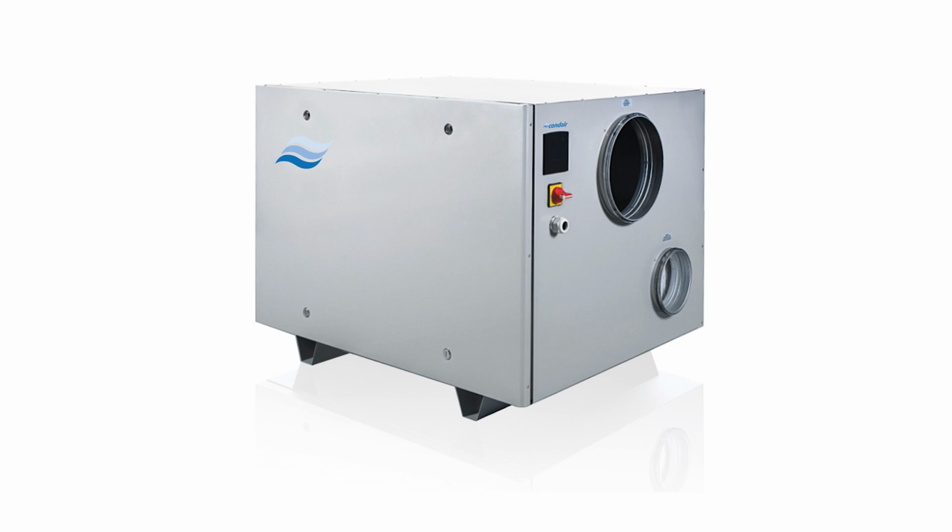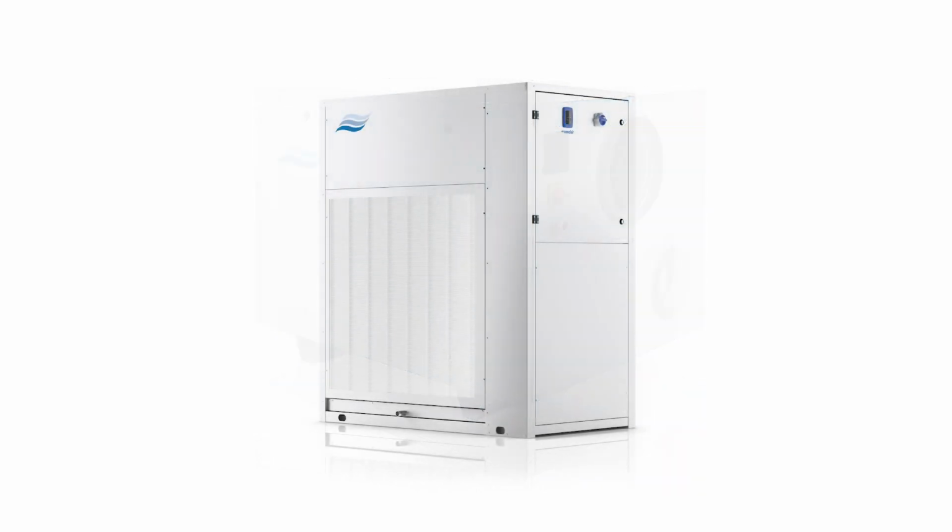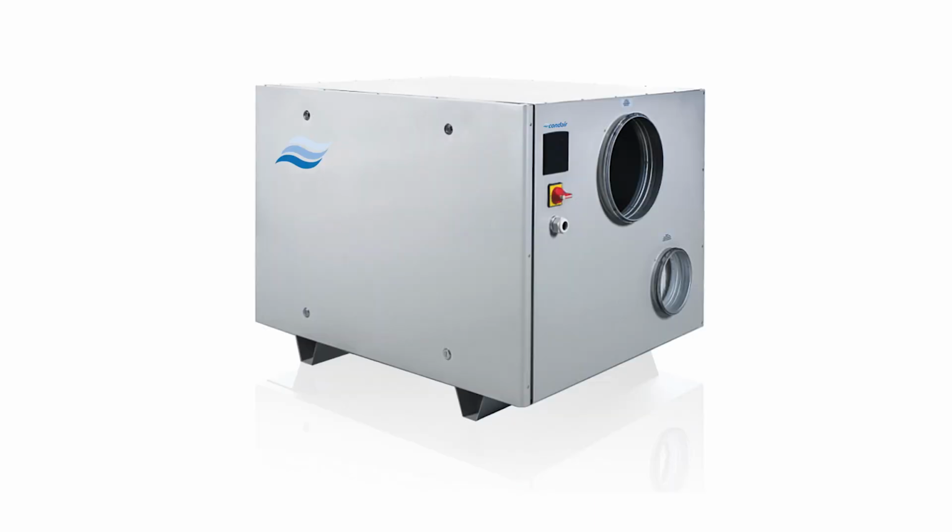which leads us nicely to our next question, which is what energy is available for drying and how much. And with the high cost of energy at the moment, the question is really important, particularly for a high capacity project. A condensing dehumidifier is typically the more efficient option of the two, as it consumes about 0.5 to 1.5 kilowatts of energy for every kilo of moisture removed, whereas a desiccant dehum will use 1 to 3 kilowatts of electricity per kilo removed. Well, that's quite a big difference, twice as much. So why such a difference?